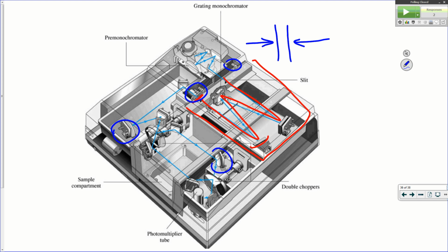If you ever take the top off of one, it's just a big black board, and it's black so it doesn't reflect light on the inside. Everything will be painted black so you don't get stray light in any way. And there's tons of screws. Every mirror has multiple screws. Typically they put something like a thread locker on the bolts to keep them from backing out. It just locks it basically, and if you have to break it loose and move it, it's really hard to do, but it keeps a bolt from backing out over time.